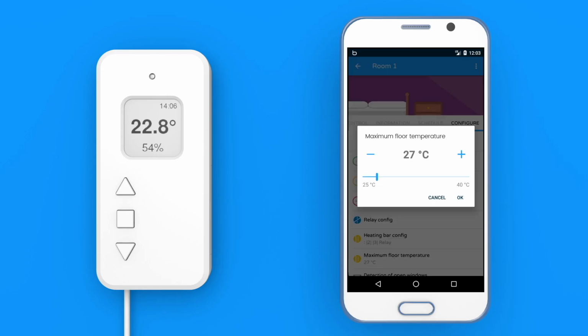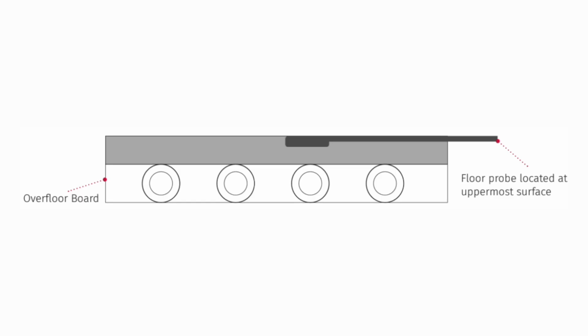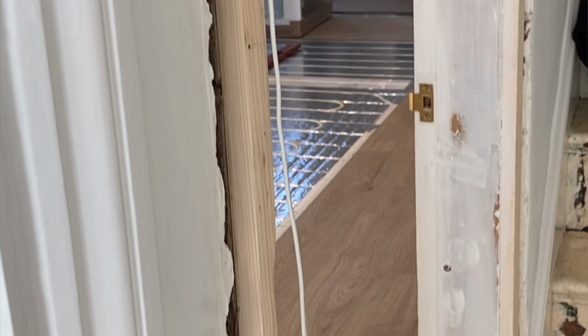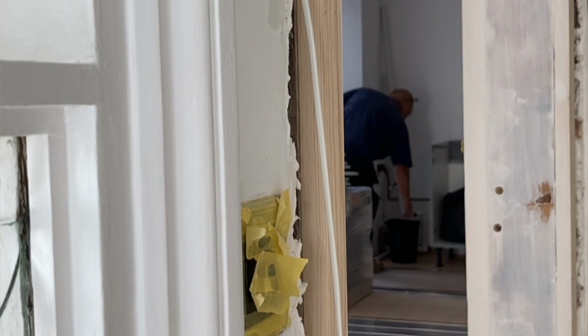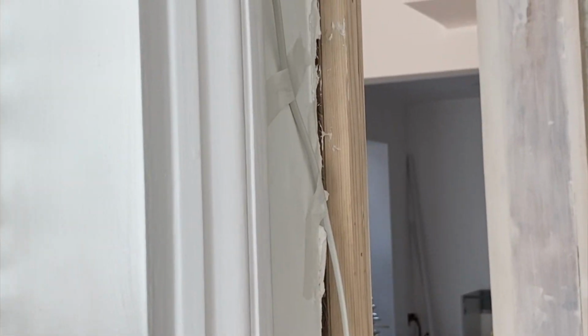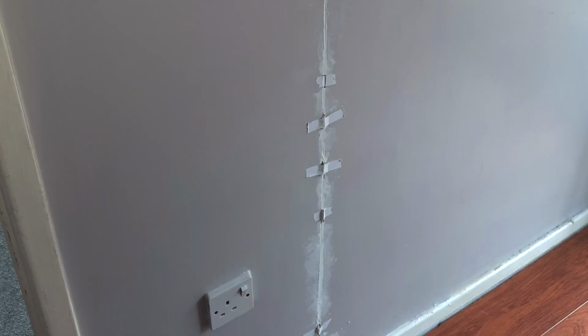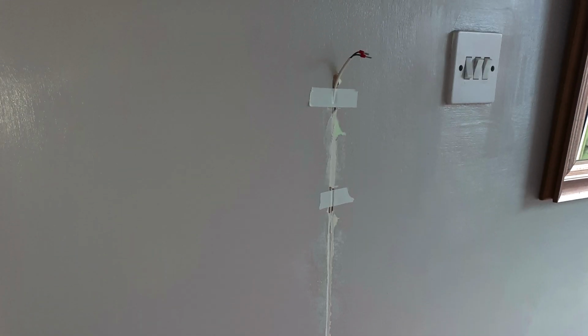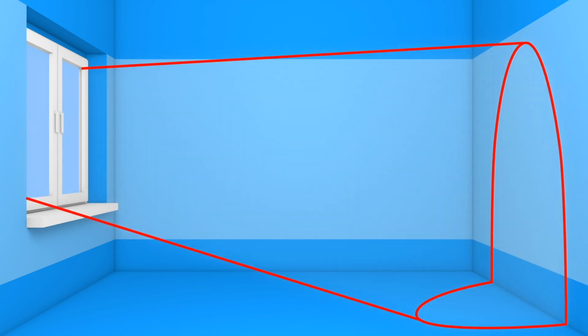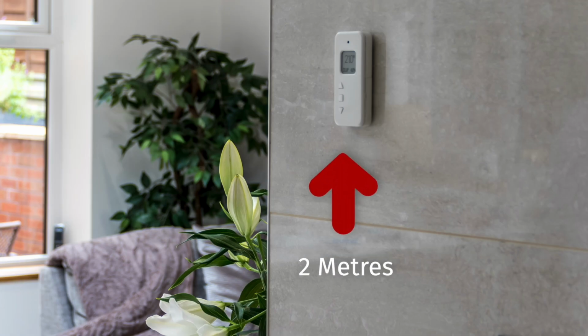The probe head must be positioned so that it will be in direct contact with the underside of your finished floor. The 3-meter floor probe cable will need to be hardwired into a wall thermostat. Therefore, before installing the probe, you must decide on the location of your thermostat, ensuring the probe cable can be safely and discreetly routed. Avoid positioning it directly above heat sources, or in areas where it might be exposed to direct sunlight. Ideally, fix the thermostat at a height of around 2 meters above floor level.